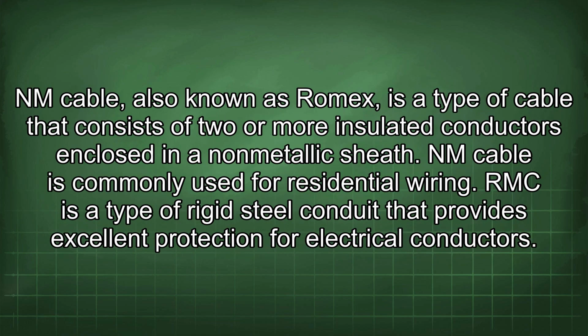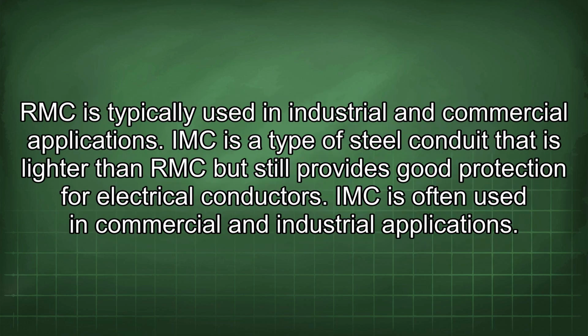NM cable, also known as Romex, is a type of cable that consists of two or more insulated conductors enclosed in a non-metallic sheath. NM cable is commonly used for residential wiring. RMC is a type of rigid steel conduit that provides excellent protection for electrical conductors. RMC is typically used in industrial and commercial applications. IMC is a type of steel conduit that is lighter than RMC but still provides good protection for electrical conductors. IMC is often used in commercial and industrial applications.